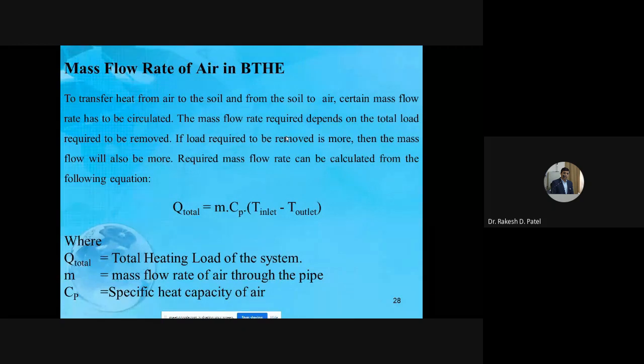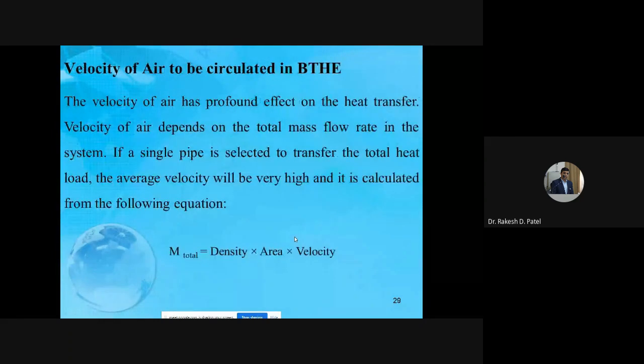Now, the mass flow rate of air in the heat exchanger. To transfer the heat from air to soil and from soil to air, a certain mass flow rate has to be circulated. The mass flow rate required depends on the total load to be removed. If the load to be removed is more, then the mass flow will also be more. I think you got my point. The required mass flow rate can be calculated from the simple equation m Cp delta T. Here m is the mass flow rate, Cp is the specific heat, and delta T is the difference between inlet and outlet of the heat exchanger. So the simple heat exchanger equation is used for the mass flow rate: Q equals m Cp delta T.